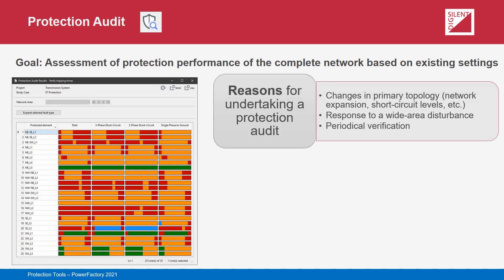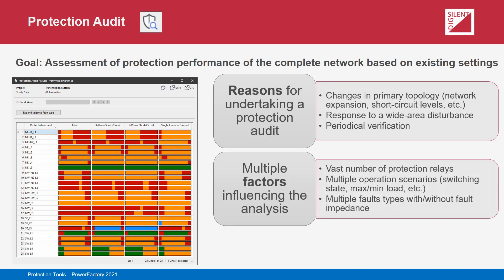Another reason for a protection audit is for periodical verification purposes, such as to help meet the requirements of standards like PRC-027-1. There are multiple factors that can influence the outcome of a protection audit analysis, and the tool has features that give the user control over the depth of the analysis. The tool is able to handle the vast number of protection relays contained within a complete grid, or can alternatively be used on smaller subsets of relays or even particular relay functions. It can be combined with PowerFactory's operational scenario capabilities to examine performance under different switching states or loading and generation states.